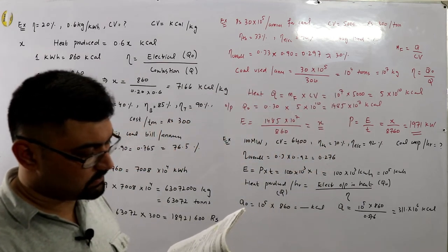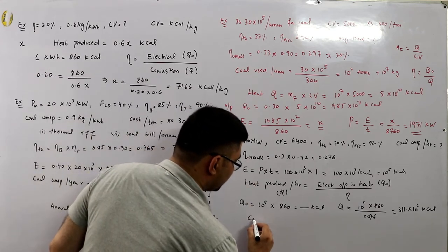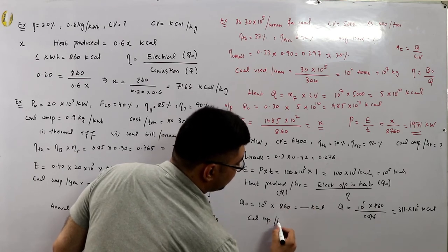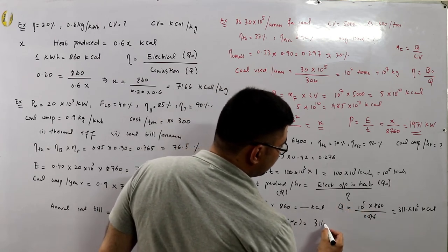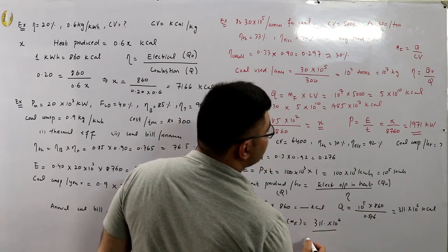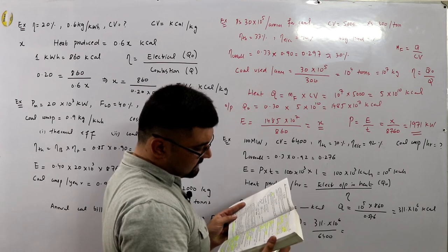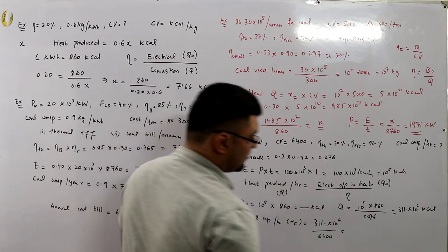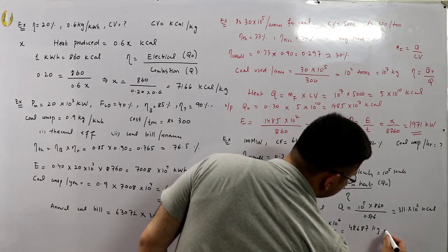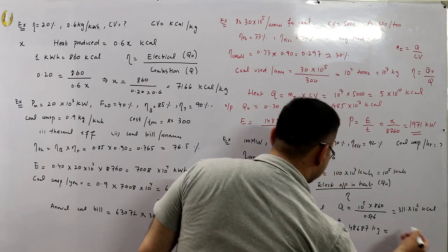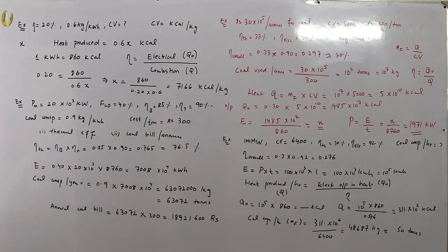Coal consumption per hour = Q / calorific value = (311 × 10^6) / 6400 ≈ 48,687 kilograms per hour, which is approximately 48 to 49 tons — the instructor rounds it to about 50 tons for safety.